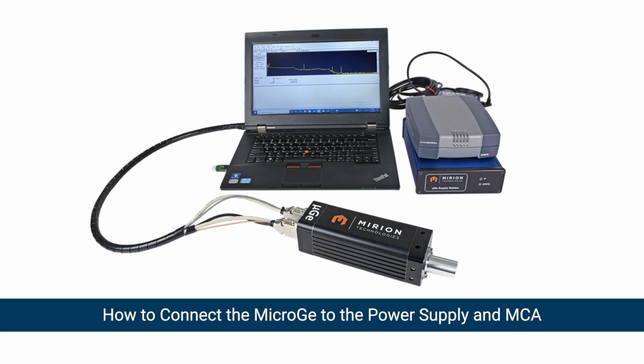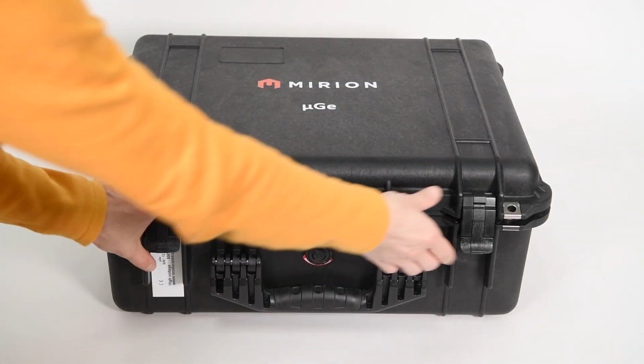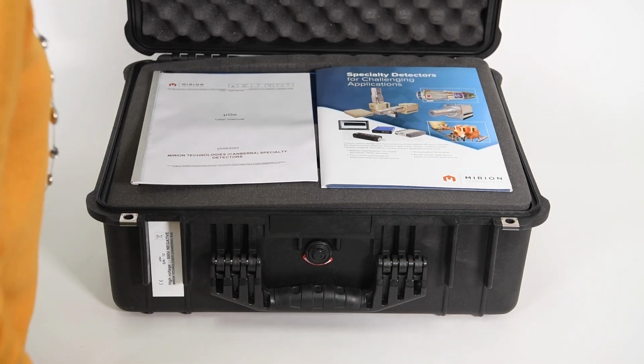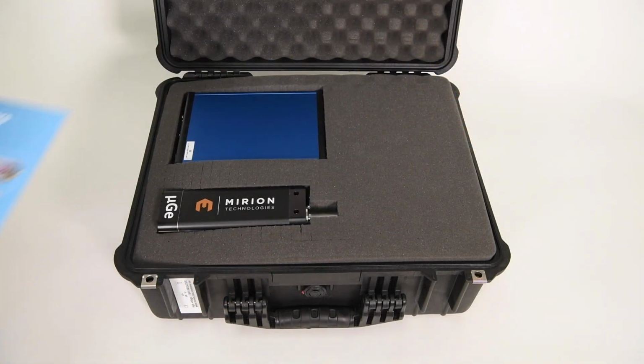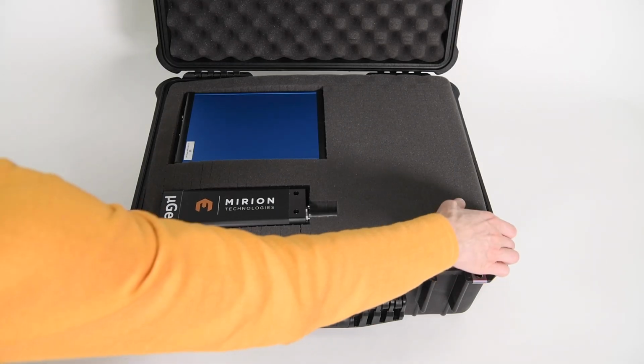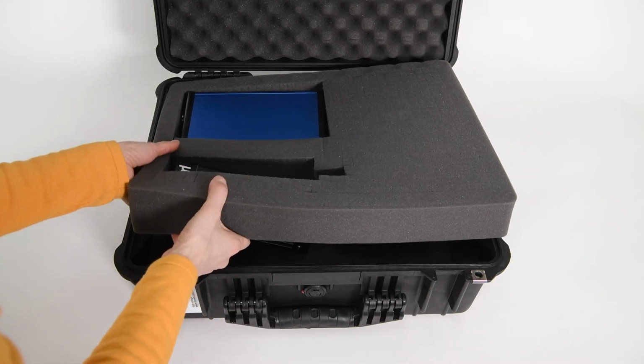Detector to the power supply and MCA, and how to cool the detector to be ready to take measurements. The MicroGe detector will arrive in a black Pelican case and will include the following items: MicroGe detector, power supply for the MicroGe detector, and a multi-channel analyzer or MCA, either the Lynx or DSA-LX. If you already have an MCA available at your facility, you do not need to order one.